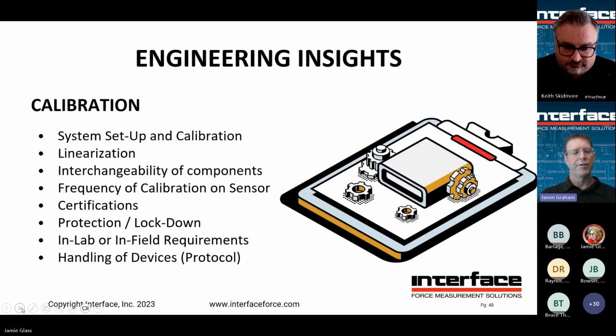So engineering insights from a calibration perspective. We have system setup and calibration. A lot of times that would be where maybe that load cell is paired with the wireless transmitter and that could be set up, so it's kind of plug and play. It's a solution where we have the calibration done, they're paired, they're ready to go, and it's provided as a paired solution.